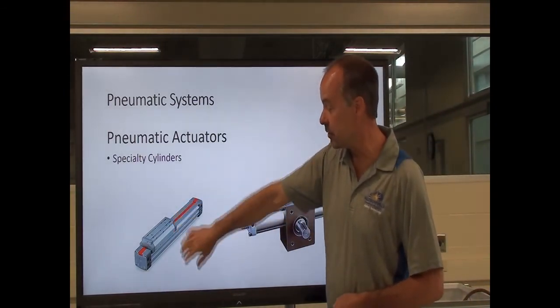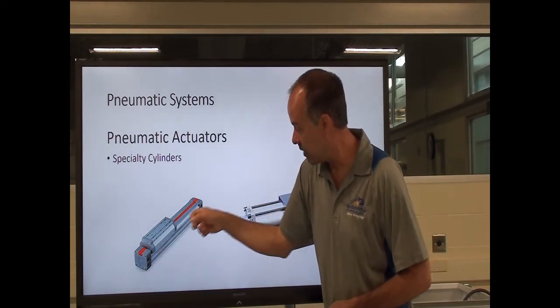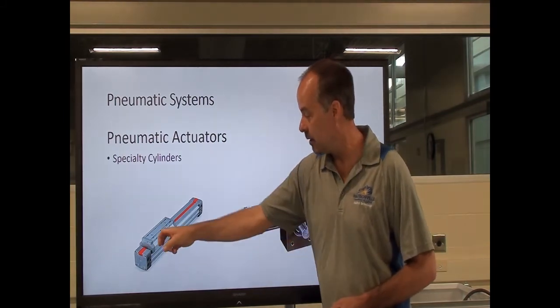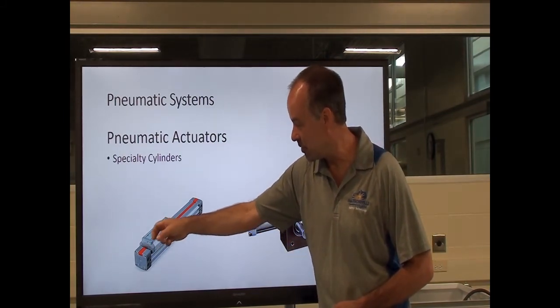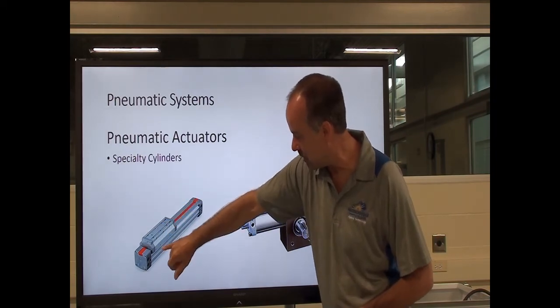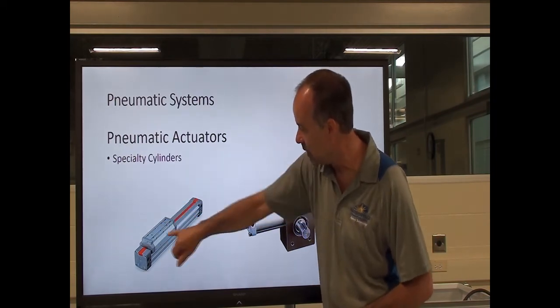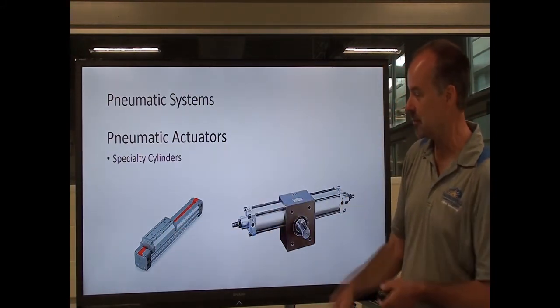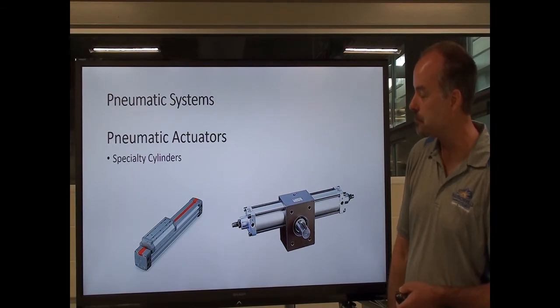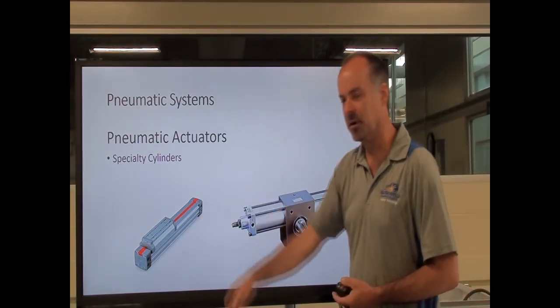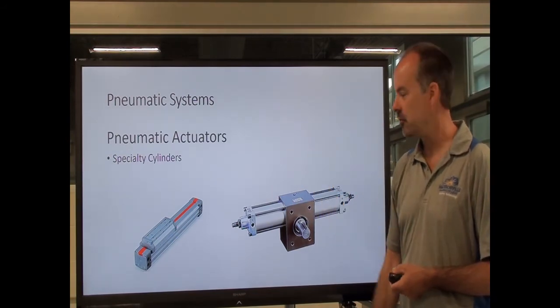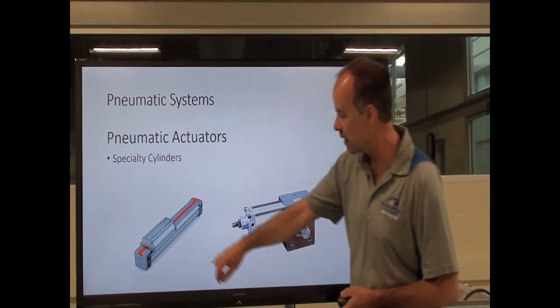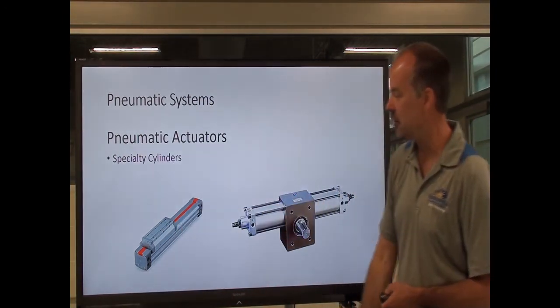Here we have a rodless cylinder. Basically, there's a piston inside this cylinder. That piston is a really strong magnet, and it actually holds this slide in position on the outside of the cylinder. As the piston moves inside, this slide moves back and forth with the piston based on the strong magnetic pull. You might find these on a piece of equipment to open and close a door automatically — any instance where you want this type of linear movement but without an exposed rod.